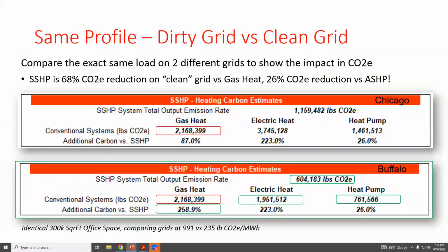Based on these profiles in different areas, we compared a water source heat pump project, full gas heating, electric resistance heating, and air source heat pump heating. You can see a general trend that a water source heat pump was overall a less carbon-intensive solution. The comparison to full gas heat seems obvious, but you can even see a good reduction compared to an all air source heat pump, due to our water-to-water equipment having much higher COPs and being significantly more efficient than air source products.